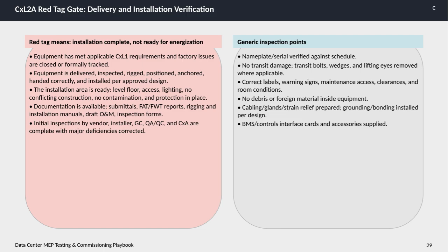The key point to understand is that a red tag signifies that installation is complete, but the equipment is not yet ready to be energized. Before moving forward, the equipment must have met all the applicable CxL1 requirements, with any factory issues either resolved or formally tracked. The equipment should be delivered and inspected thoroughly. It needs to be rigged, positioned, anchored, and handed over correctly, all according to the approved design.